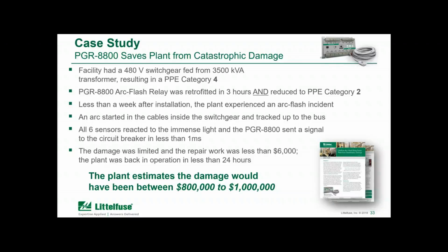And it did successfully limit the damage, with repairs costing less than $6,000 and only 24 hours or less of downtime. So the customer, in talking with them, estimated that the downtime, without having a device like that, would have been weeks or maybe even months, with repair costs that could have approached $1 million. So implementing an engineering control like arc flash relays can have a dramatic impact on the safety and also provide some good insurance for the facility.